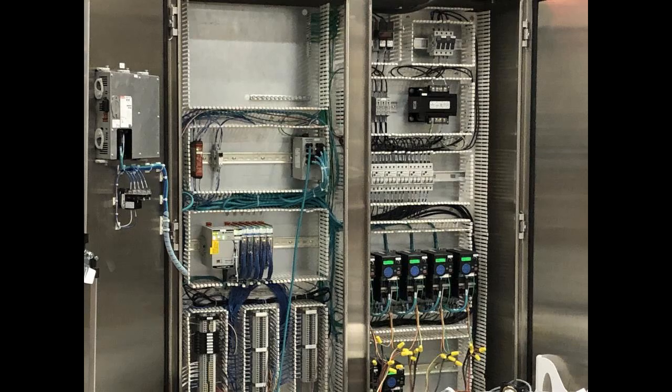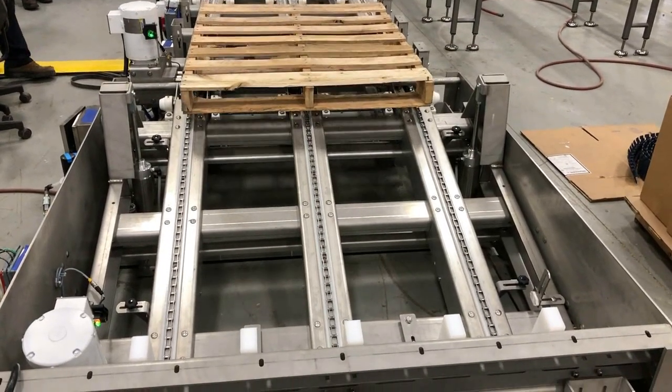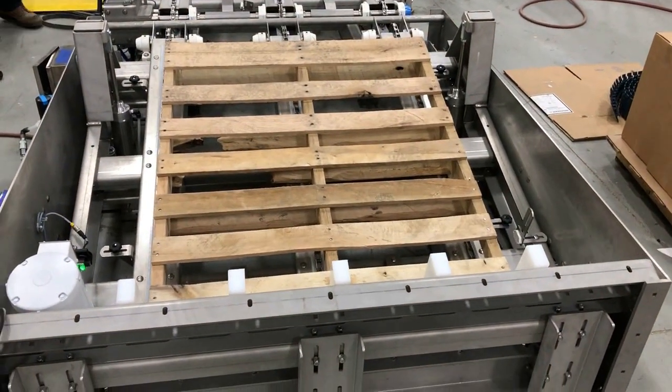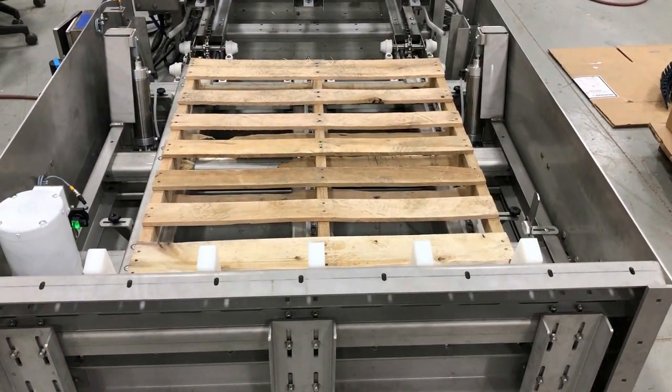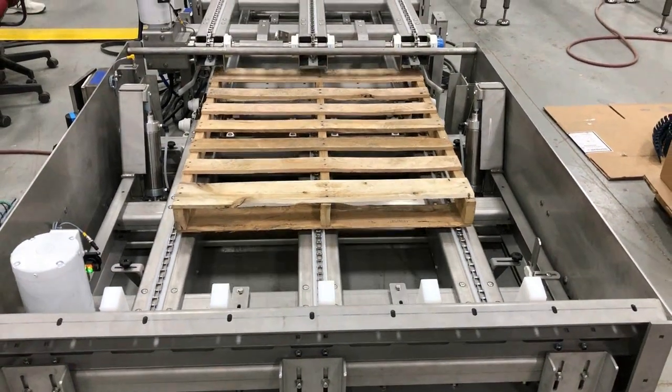Multiconveyor provided stand-alone electrical controls for the entire pallet conveyor including a UL-listed control panel with through-door disconnect, Allen-Bradley CompactLogix Processor, PowerFlex 525 VFDs, PLC Safety Relay, PanelView Plus 7 touchscreen display, and e-stops.